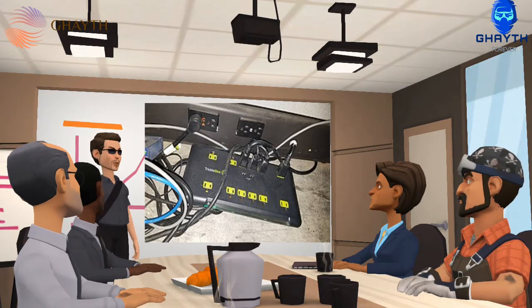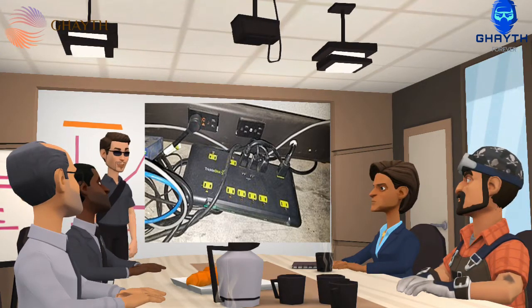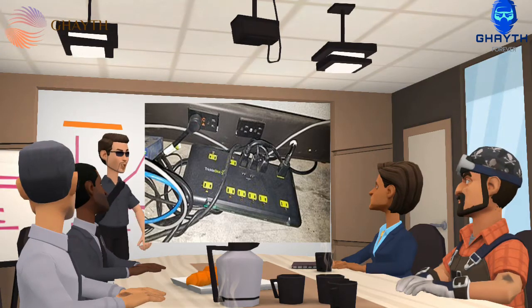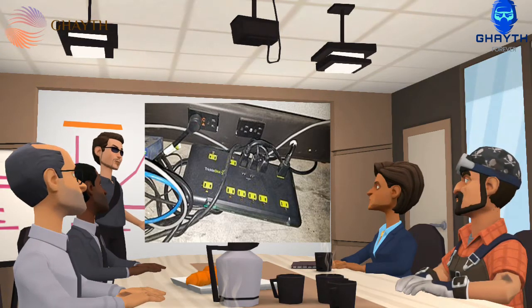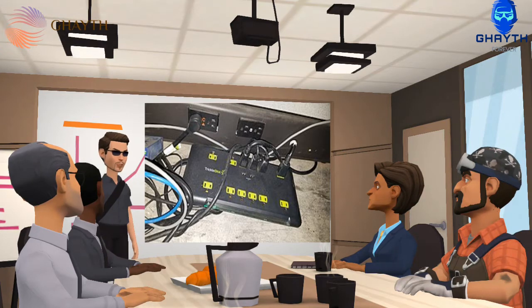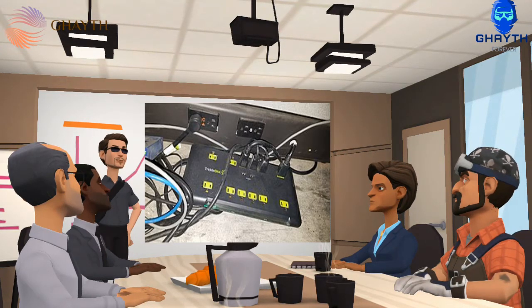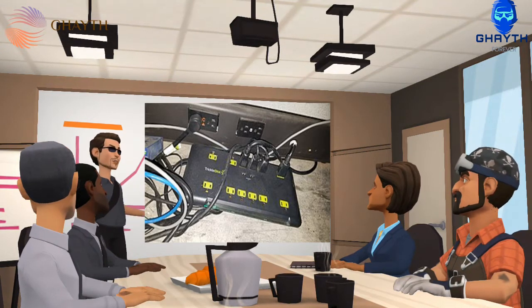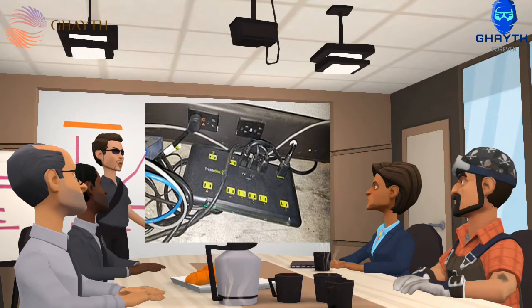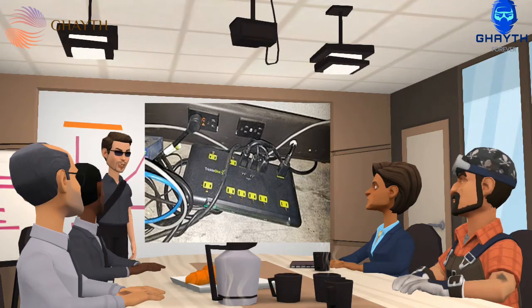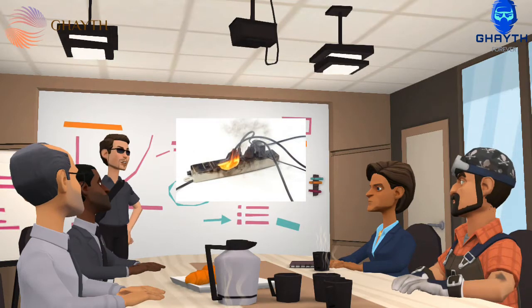Long-term surges can destroy the protectors in an entire building or area. Even tens of milliseconds can be longer than a protector can handle. Long-term surges may or may not be handled by fuses and overvoltage relays. A transient surge protector attempts to limit the voltage supplied to an electric device by either blocking or shorting current to reduce the voltage below a safe threshold.